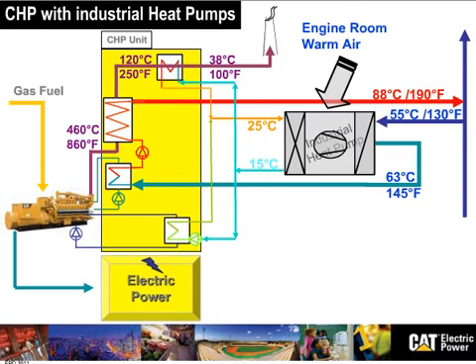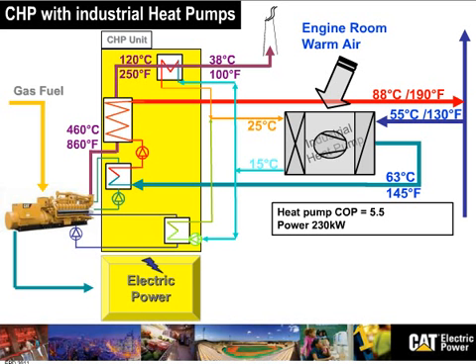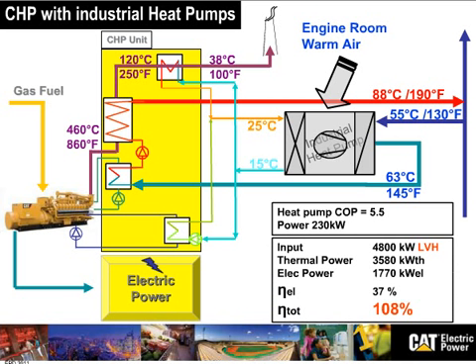You can see here on the center of the drawing, water at 25 degrees from the residual exhaust gases or the low aftercooler part of the equipment, and also the hot air from the room. Both, this heat pump will raise it to a useful temperature range that you can actually have a value for. So if you look in details, these typical heat pumps are popular here, especially in Europe. The coefficient of performance, COP, is very high. It's a screw type of heat pump. The electric power you need to feed that heat pump is 230 kilowatts here. But the beauty of the heat pump and the CHP is now you can raise the efficiency above 100%. Well, there is no magic here. 100% is on the LHV, and then since we condense and take more heat than the LHV, it's 108%. So that's the beauty of using LHV or HHV.